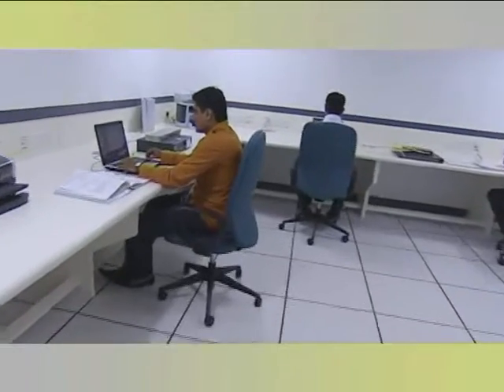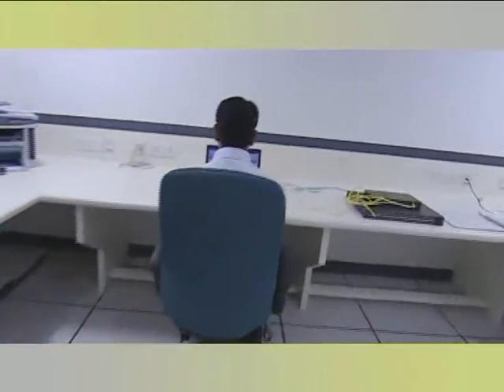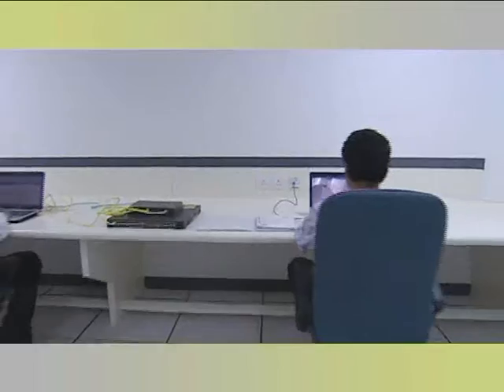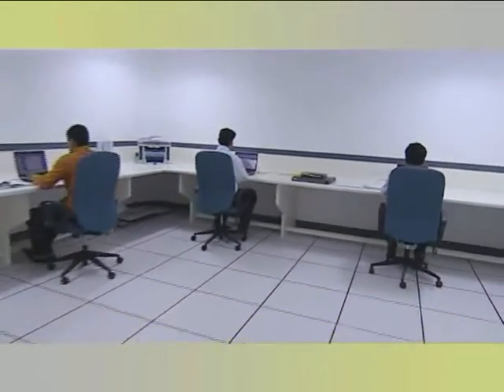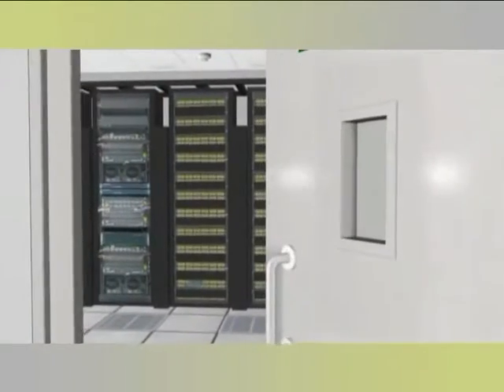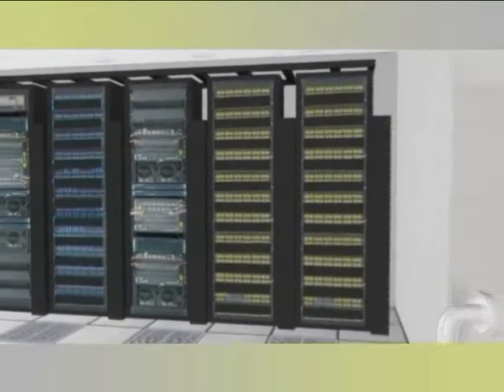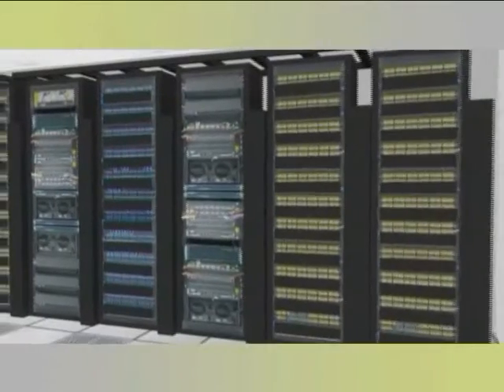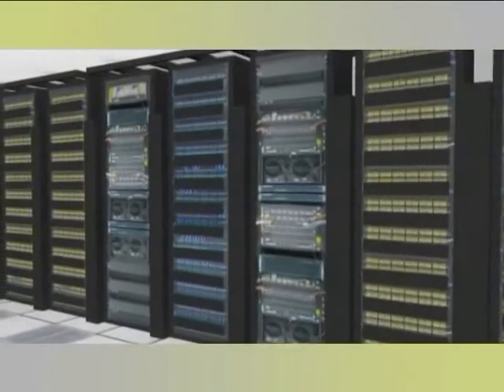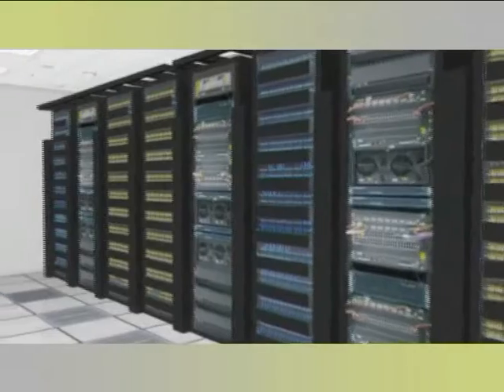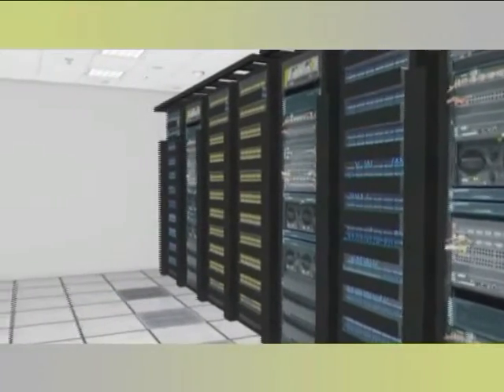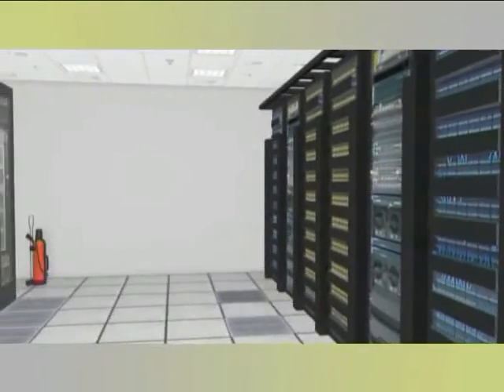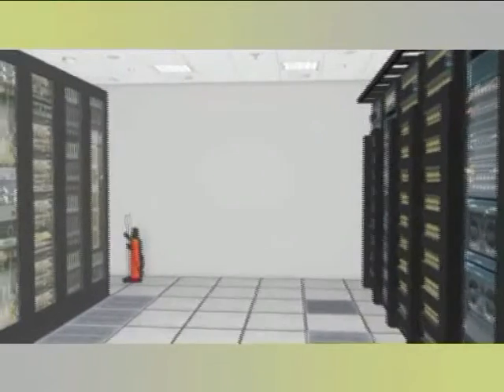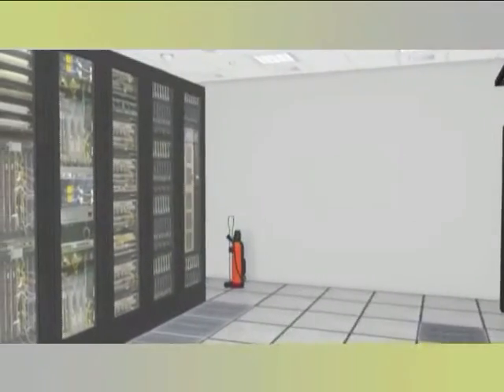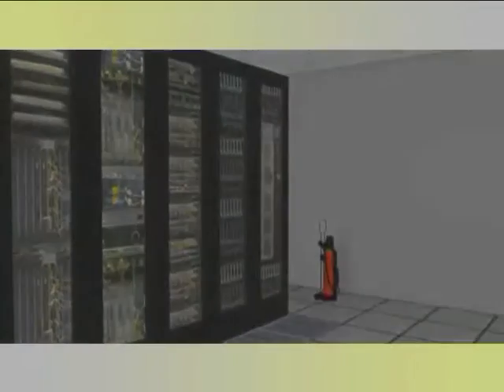Prior to co-location in the server halls, all devices are housed in the staging room, where the basic inventory checking, installations and upgradation of the devices are carried out. The data center has network connectivity with all major telecom operators. This carrier-neutral feature facilitates extension of our clients' links from service providers into our data center network. High-end devices like IPS, firewalls, routers, server load balancers and switches have been installed in a redundant architecture. This guarantees a highly available network infrastructure at the data center.